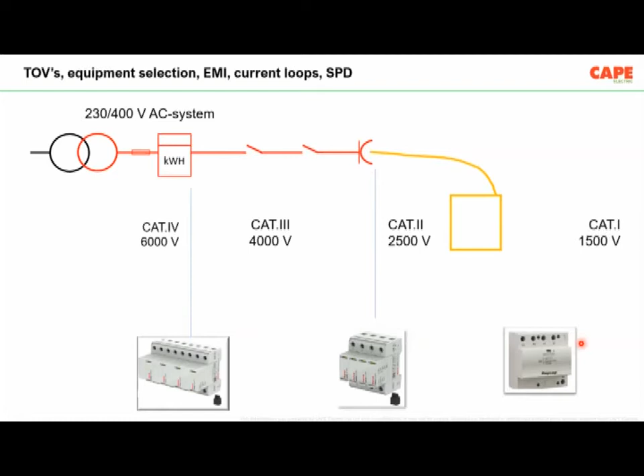Whenever there is a fault on the HT side of the transformer, there can be problems. TOV at the equipment means the equipment may burn. People may get a shock. Somebody touching an equipment may get shock. A good electrical installation must have protection against this problem number 1. That means whenever there is an electrical fault at the high voltage side of the installation, low voltage equipment must withstand it. And the permissible power frequency stress voltage is 1200 volt up to 5 seconds.